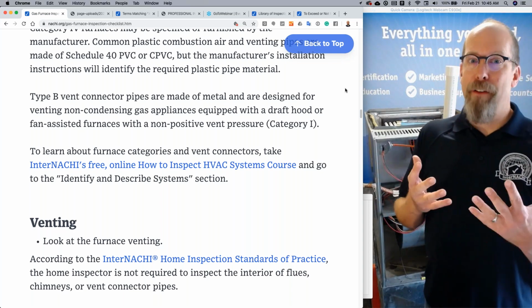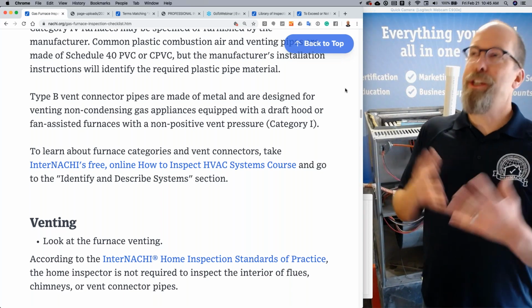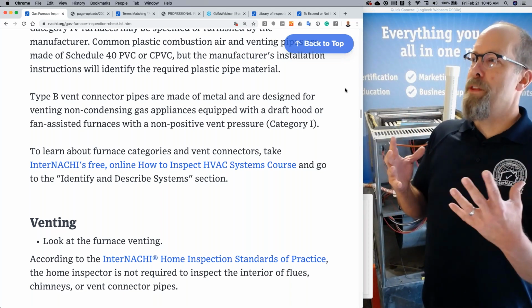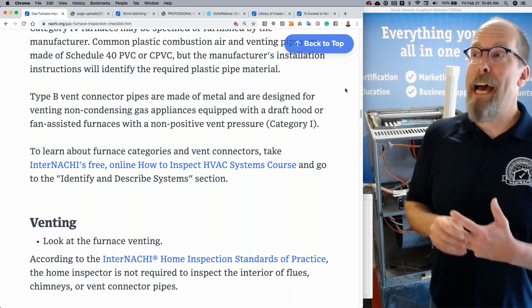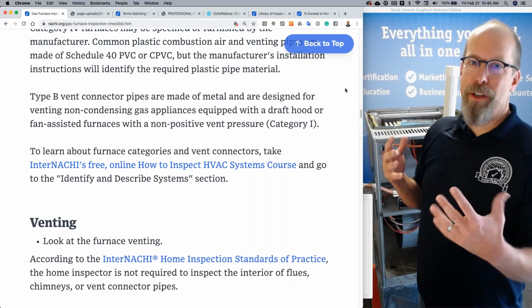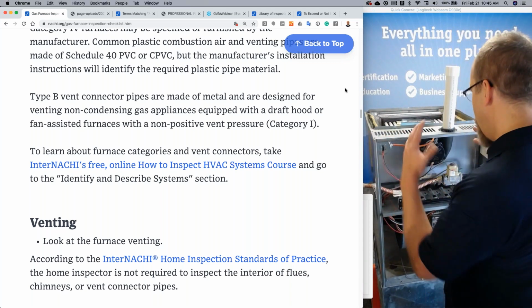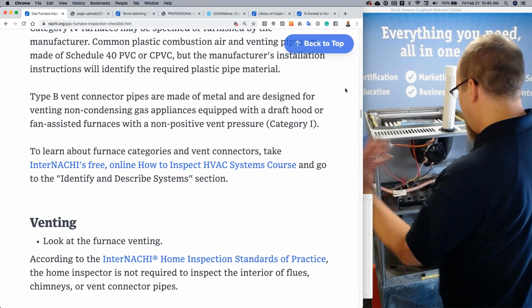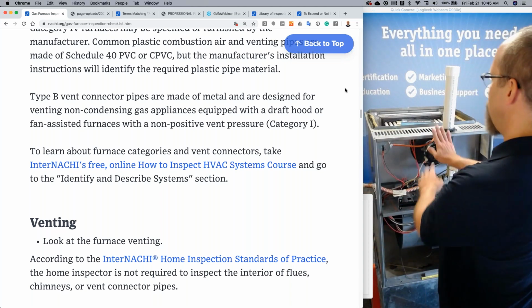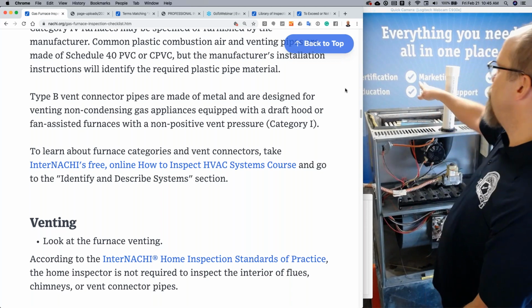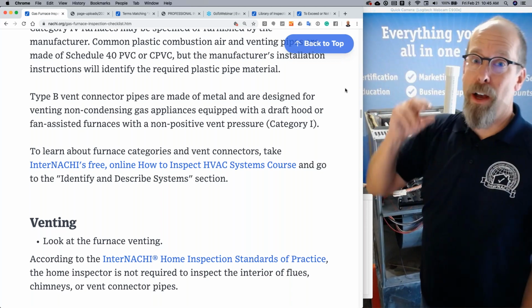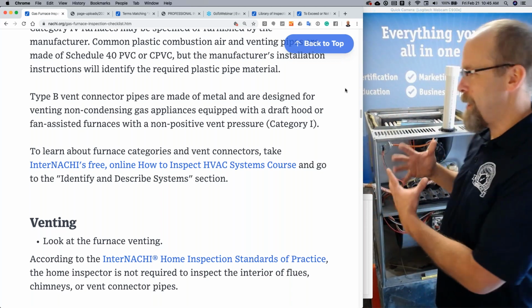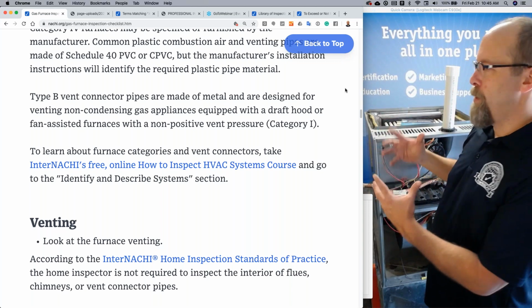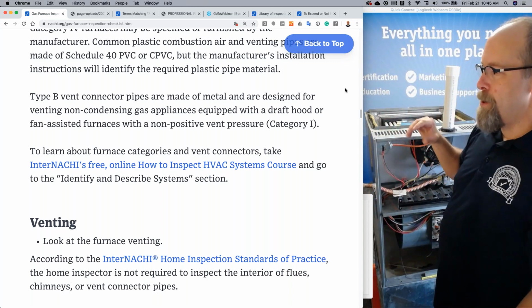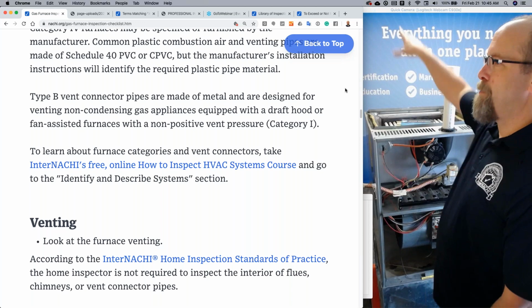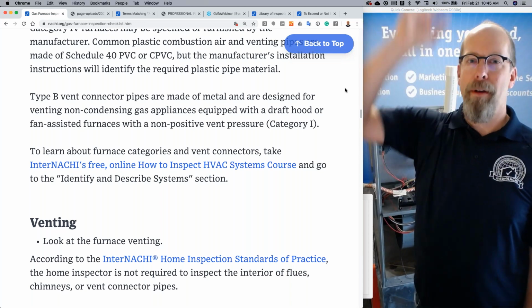That's a negative vent pressure. The chimney is essentially filled with hot air, and hot air rises, like natural draft furnaces, which are not made anymore. There's a hood that allows air to go into the vent hood through the chimney stack, and it just drifts up because hot air rises, and it's buoyant. It's like a hot air balloon, right? And it's non-positive pressure, negative pressure. That's why it goes up, right?